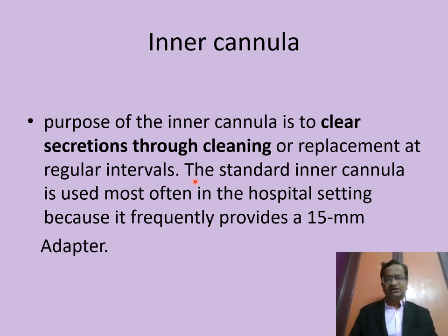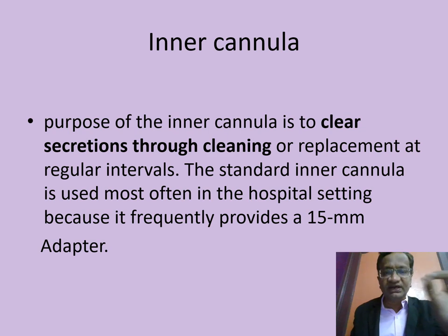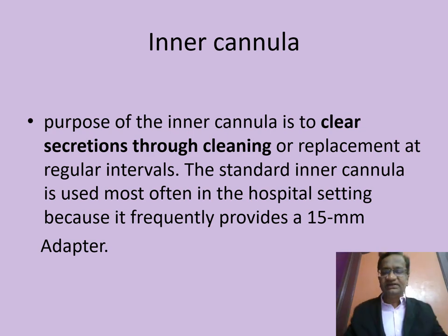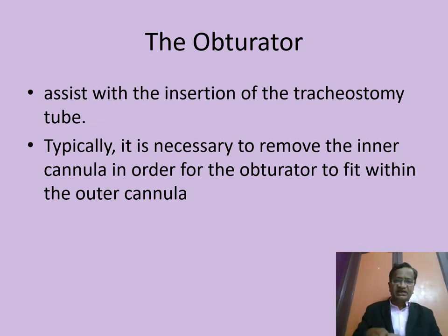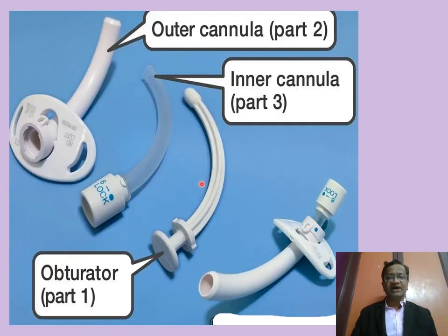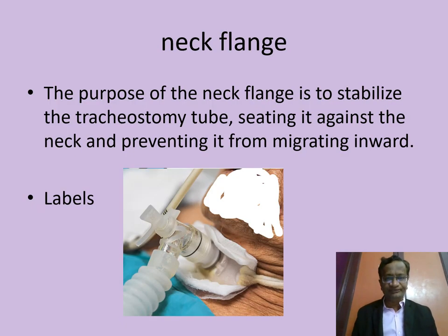The inner cannula is designed to clear secretions through cleaning or replacement at regular intervals. It contains a standard 15 mm adapter. If it becomes blocked, remove the inner cannula, clear it, and reinsert it to resume ventilation. That is the purpose of the inner cannula — to handle secretion blockage.